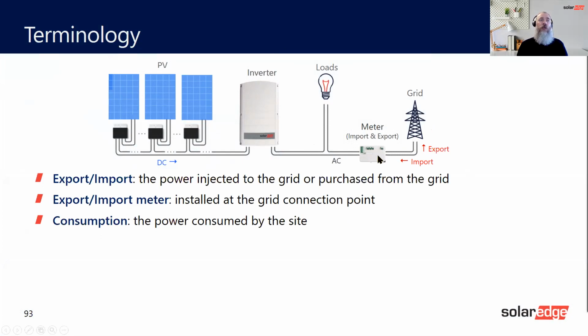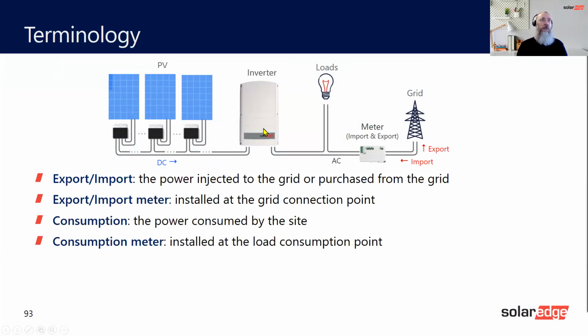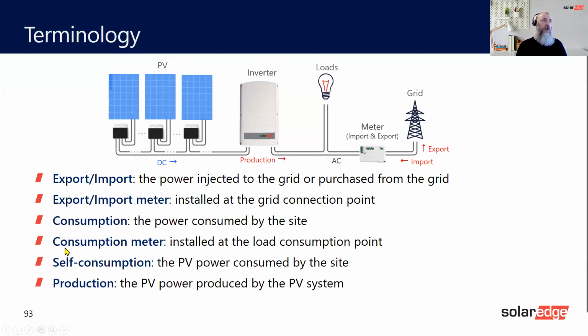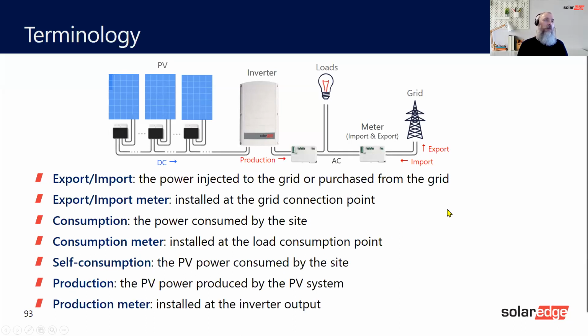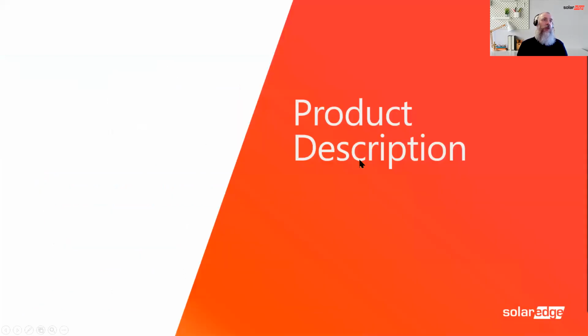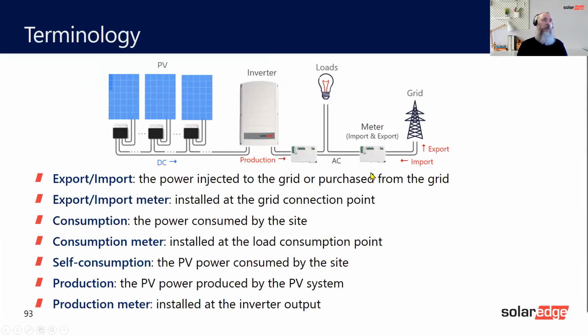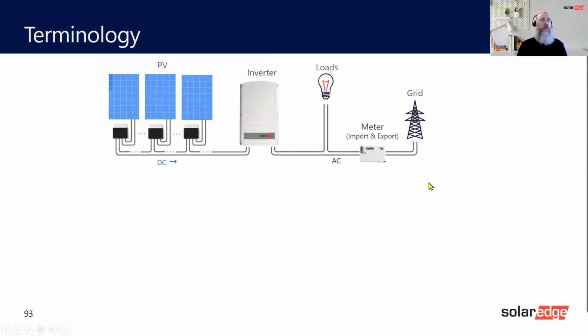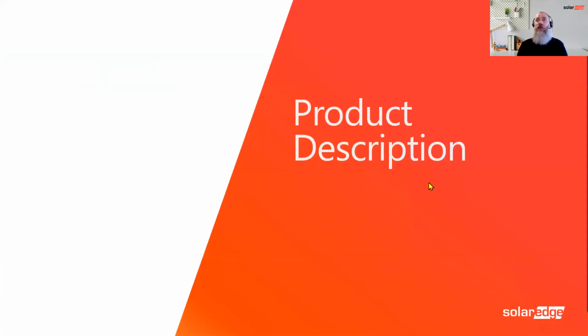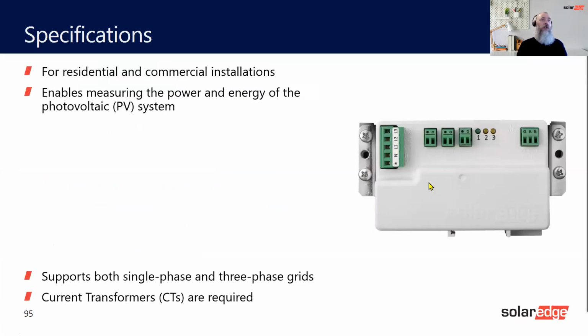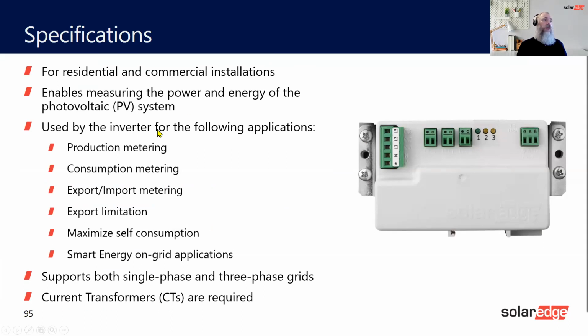So export and import is basically what goes to the grid and what comes in. Very good information that the inverter needs, because then it will tell the battery whether to charge or discharge. The other terminology is consumption, consumption meter, self-consumption, and production. So you can do all this with the meter as well, depending where you put it. But we mainly want it on the import and export here. Oh, wrong way. So product description, let's have a look at it. For residential and commercial installations, it can do all the things we've just spoken about. We need it for maximum self-consumption, for export limit, things like that.